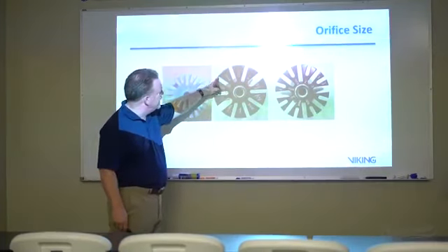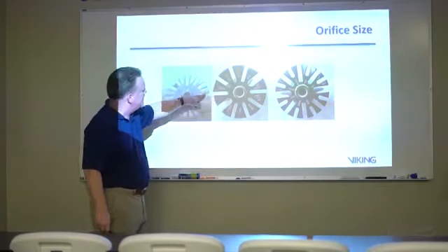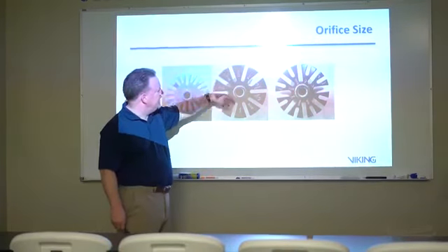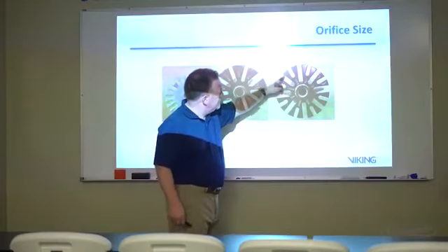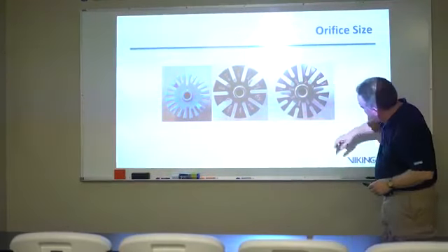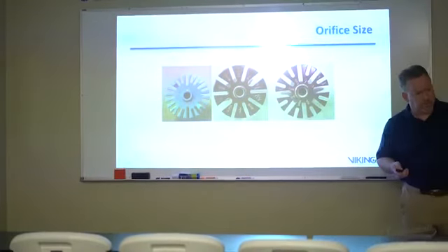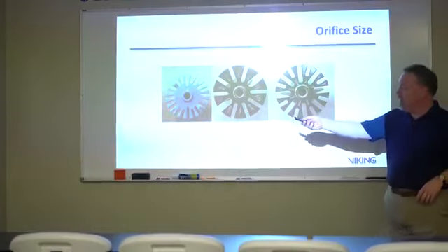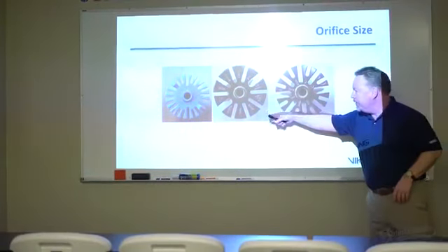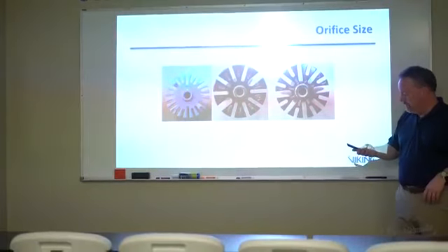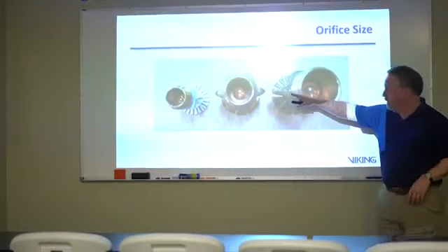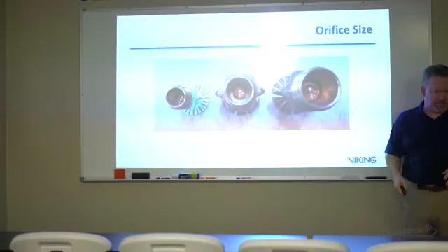But as we look at this one, then we come over here. This middle sprinkler was an ESFR, VK500, K14. The one on the far right was a K factor of K18, K18. And the 472 is a 5.8. So we have a 5.8 K factor, a K factor of 14, and a K factor of 18.6 it looks like. Smaller, middle, large. And they even go bigger than that.